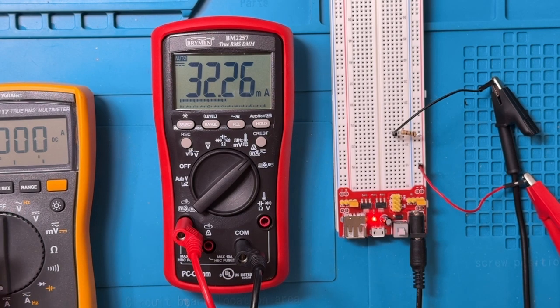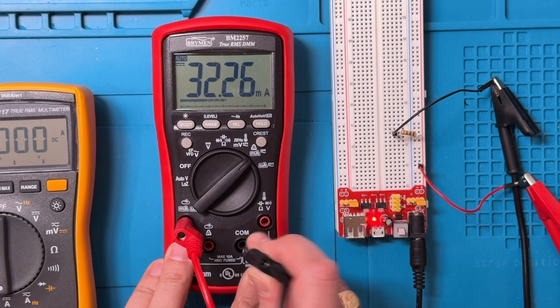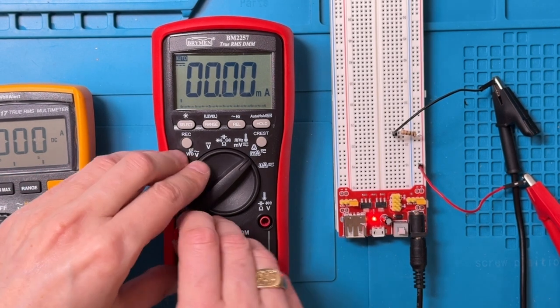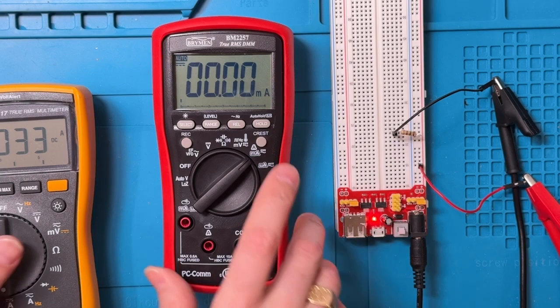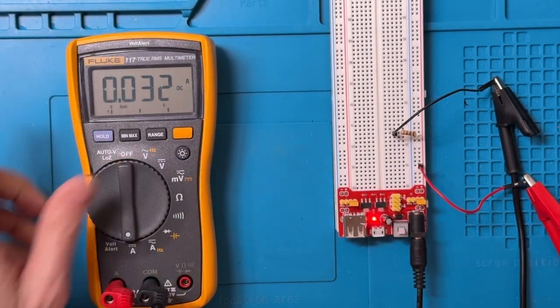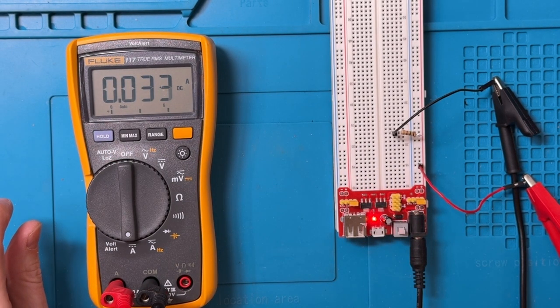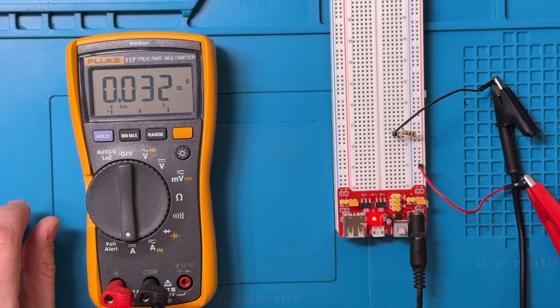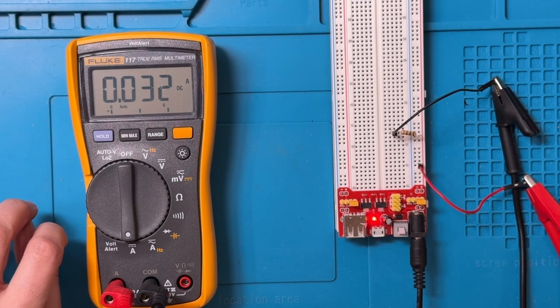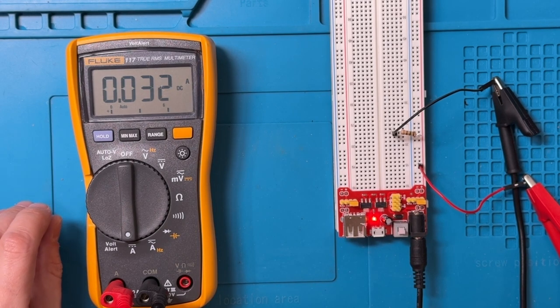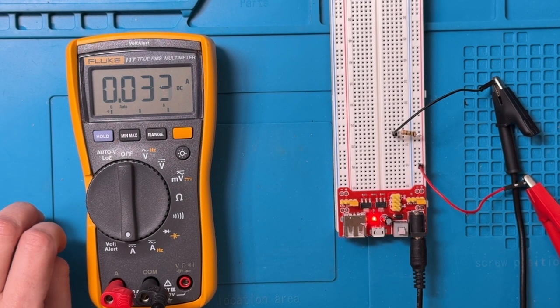Now we can take that over to the Fluke. The Fluke only does amps, it doesn't do milliamps. So the Fluke varies a little bit between 32 and 33 milliamps. It's a little bit tough to tell whether that's a result of the impact of the leads, or whether the Fluke is a little more accurate.